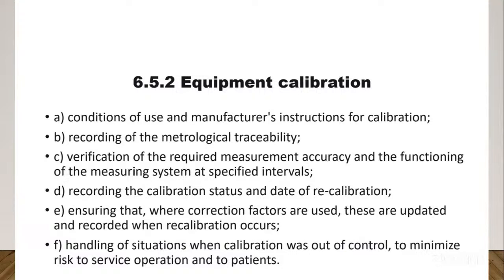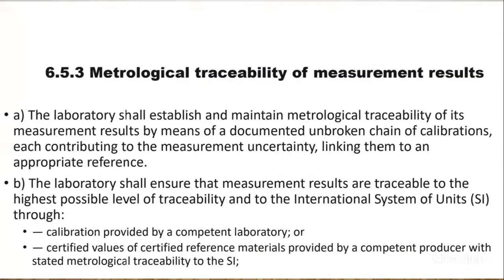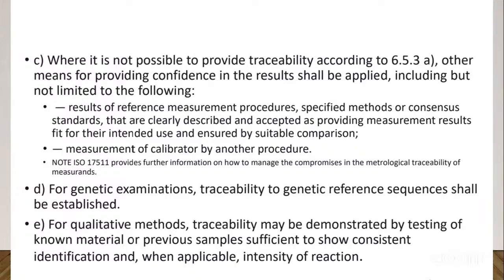Most of the equipment, you can't use them without calibration, and those ones that you need to recalibrate, it's very, very important. And handling situations where calibration was out of control, to minimize risk to service operation. So when the calibration fails, most of the equipment may not even function. And I've talked about the traceability of the measurement we are doing, and it's very important that calibration should be provided by a competent organization. When it's not possible to provide traceability, for providing confidence in the result, a reference material procedure can be used when you don't have the traceability record.